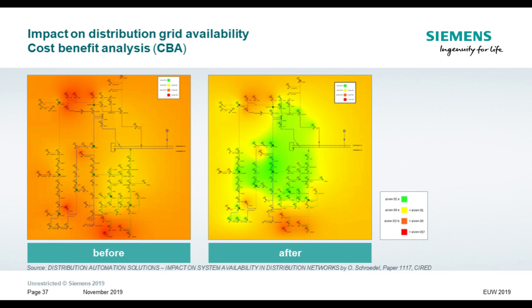After automating around 15% of the stations, the important stations, you already see the outage times decrease a lot. In the inner circle, where we have closed-loop connections and radial ring connectivity, we can switch immediately in under 1 minute, or even in some seconds, depending on the switching devices we have.